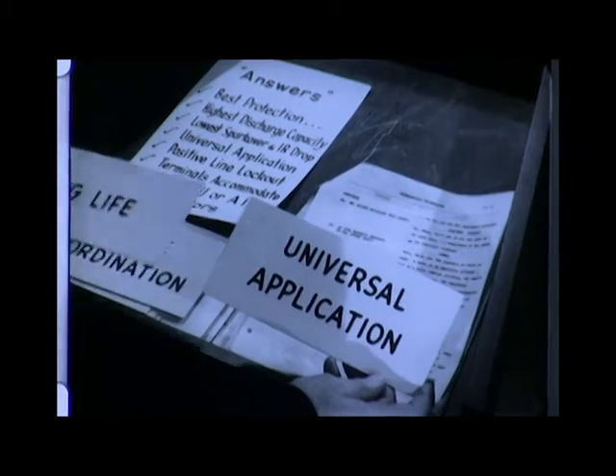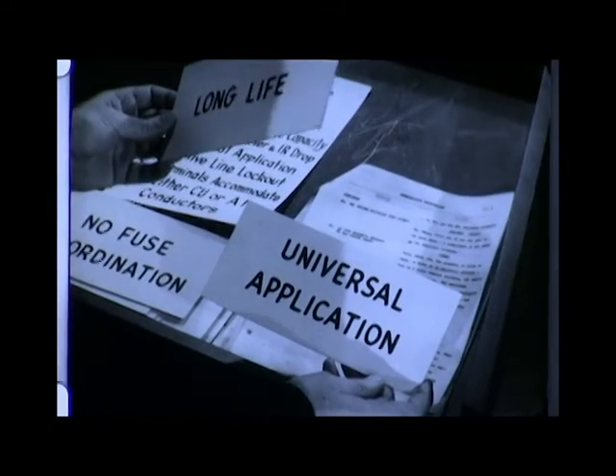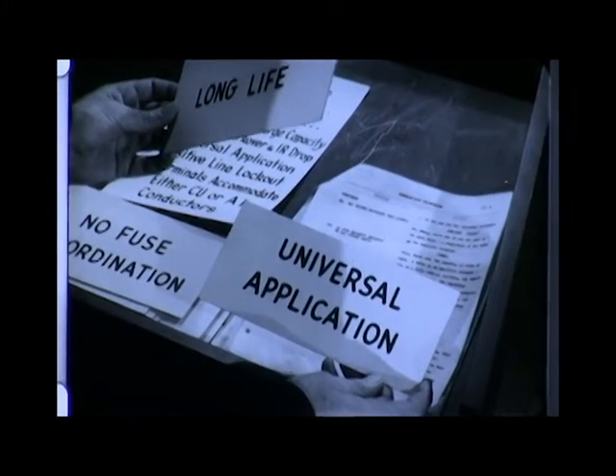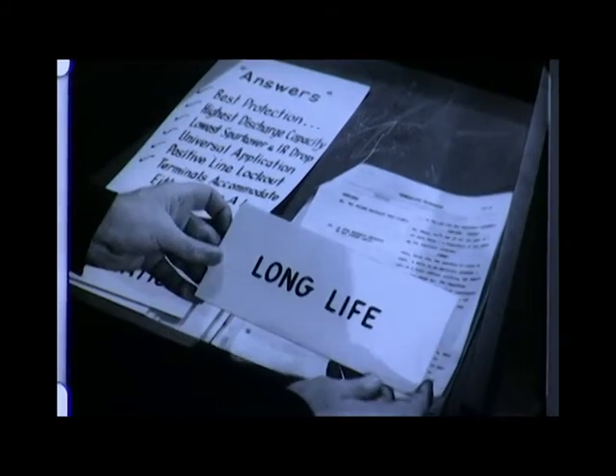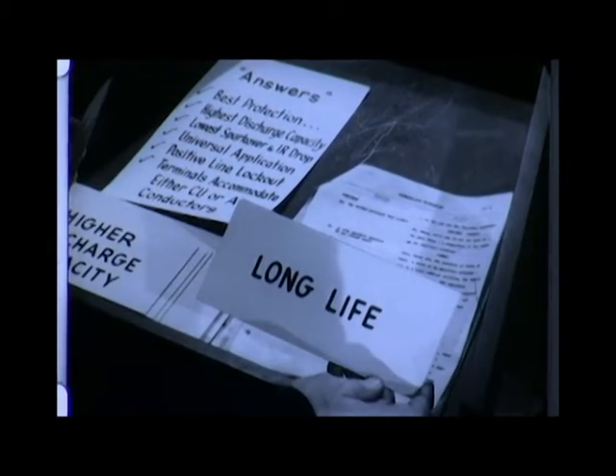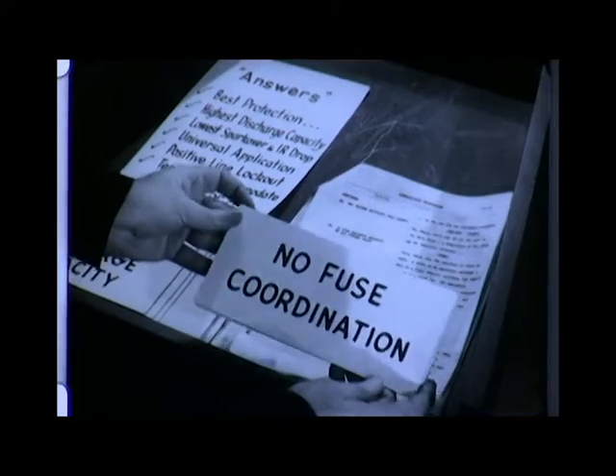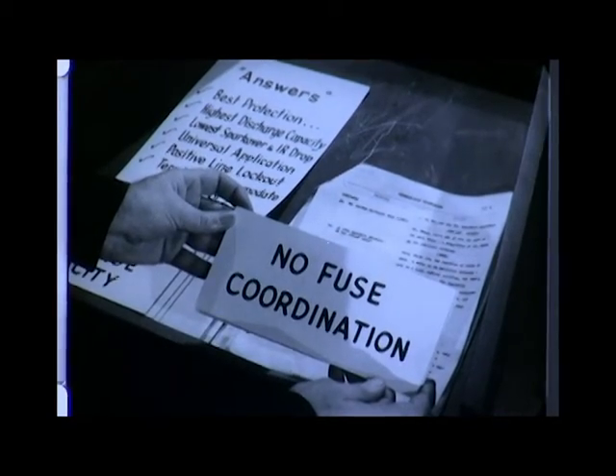Of course it's right. Now, as for valve arrestor advantages, they are: 1, universal application—you can hang it anywhere on your system without regard to available short-circuit current; 2, long life, as there is no erosion taking place; and 3, you have no fuse coordination problem with a valve arrestor. Should also mention lower impulse spark over. Of course, the General Electric Magna-valve arrestor incorporates the best features of both the valve and expulsion types.